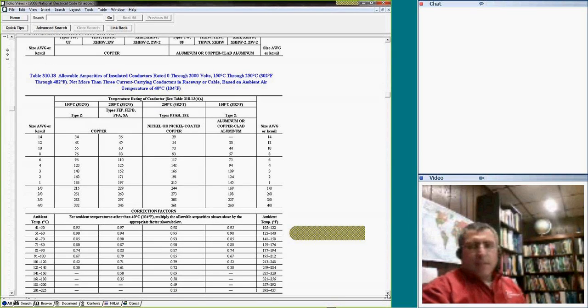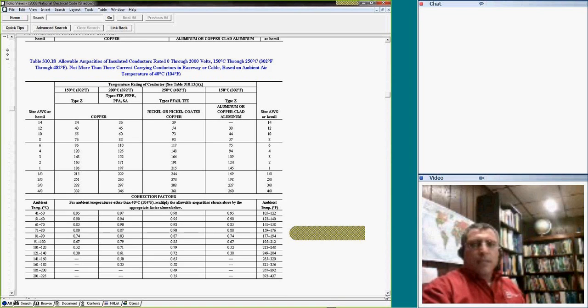How many have used high temperature conductors? Anybody? You're looking at it right in here. A conductor that's rated for 150, 200, or 250. So these are the high temperature conductors. The types are Z, ZF, PFA, and so on.